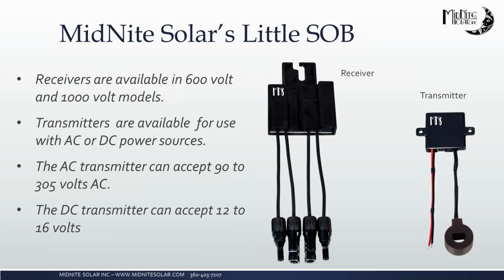the models that we offer. They are available in 600 and 1000-volt models for the receiver, and the transmitters are available in AC or DC power sources. So if you choose the AC, you can use anything from 90 to 305 volts. And with the DC transmitter, it can accept between 12 and 16 volts for a power source.